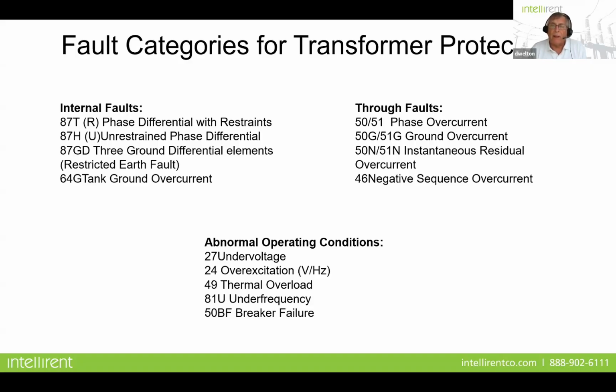If you look at a multifunction protective relay for a transformer, you have three protective zones. One is for the internal faults of the transformer itself. This is usually done by certain relays that we refer to as phase or ground differential relays. So current going in equals current coming out, and we know there's no internal fault in the transformer itself. The other are through faults, and these are transients that go through the transformer, something occurring outside the protective zones of the transformer itself. And then we have abnormal operating conditions, things that just happen during the normal operation in a substation that can be a challenge or could damage a transformer.